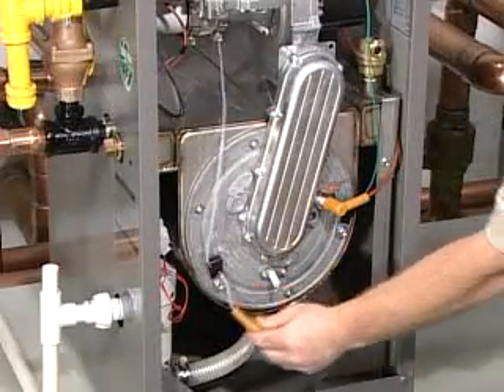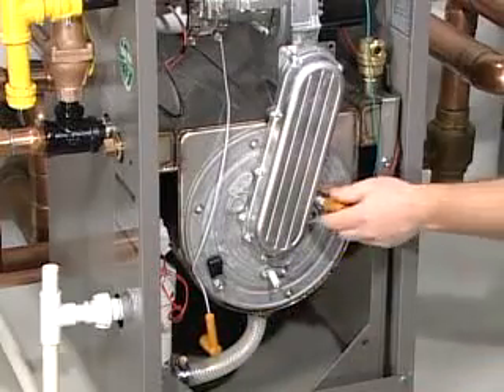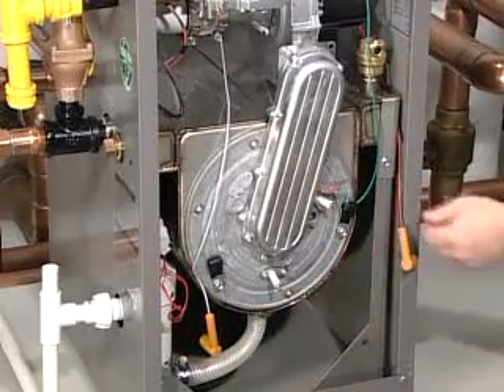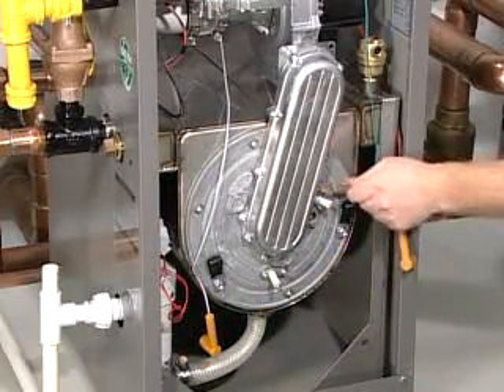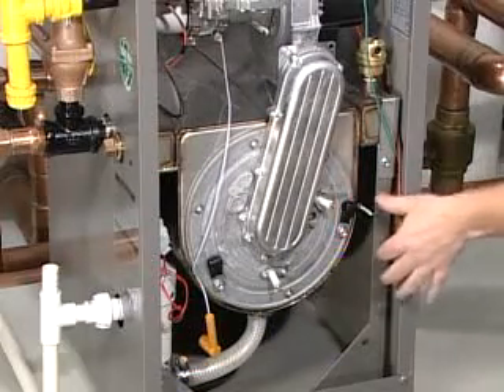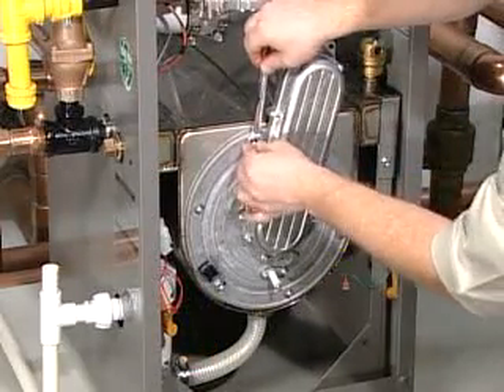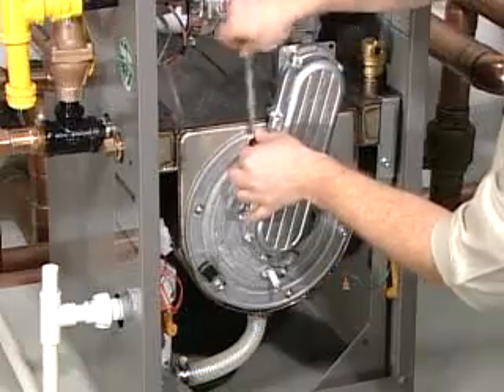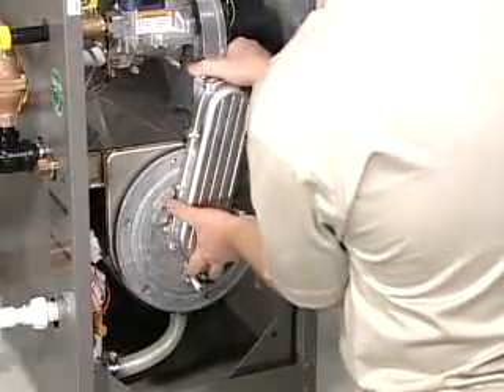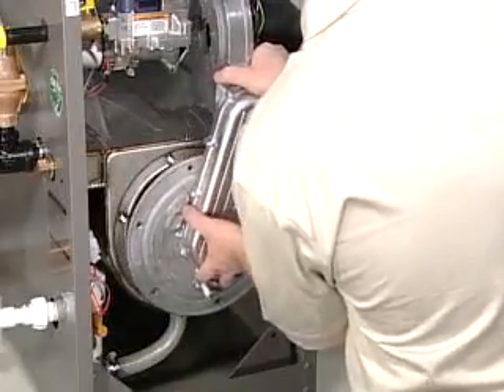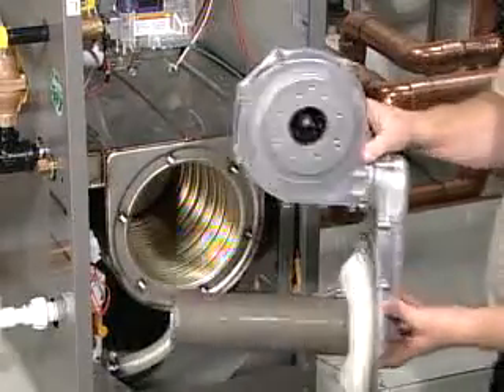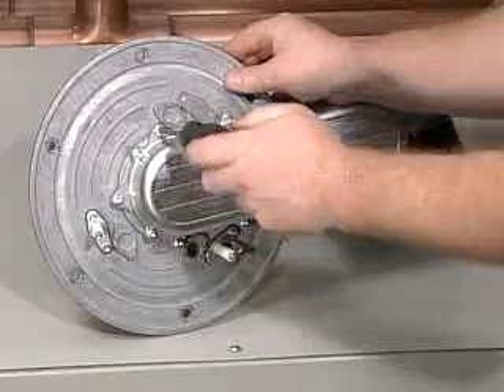Remove the wiring from the flame rod, spark igniter, and ground terminal from the front of the heat exchanger door. Using a 10 mm socket or wrench, remove the 6 nuts securing the heat exchanger door to the heat exchanger. Carefully remove the heat exchanger door with the blower and gas-air arm still attached.